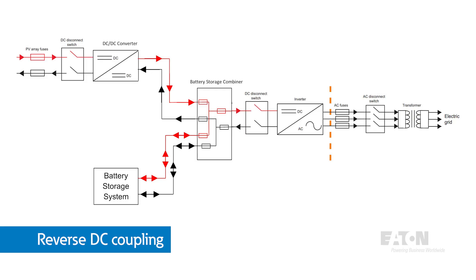Reverse DC coupling is similar to DC coupling, except that instead of a DC-DC converter on the battery storage system, the DC-DC converter is on the PV circuits before connecting to the battery storage circuit. This is the least commonly used design, largely due to a lack of equipment suitable for this application. In reverse DC coupling, PV-listed overcurrent protective devices are required up to the input of the DC-DC converter, and then everything on the output of the converter is required to be suitable for battery storage applications.